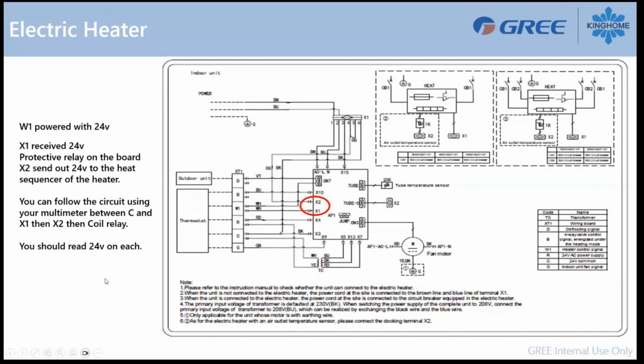So what's going on with the electric heater when it's time to put it in place? The relay here has a safety or trigger condition to power up your duct heater. First of all, there is a feedback signal from the duct heater, and also you need to have the fan running to make sure the board will give you the authorization to start the duct heater. So the fan blower must be active before you try to power up your duct heater.